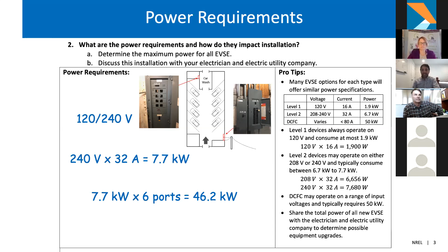Each new EVSE needs its own branch circuit. Looking at the SAE standard, level 2 can actually demand an 80 amp maximum, so technically the maximum current to a level 2 station is 80 amps, not 32, which is most common. But 32 amp is very practical because 40 amp circuit breakers are common and simpler to install, and easier for sizing the service panel. The biggest consideration is making sure you have sufficient breaker capacity and service panel capacity for all the breaker positions you require.